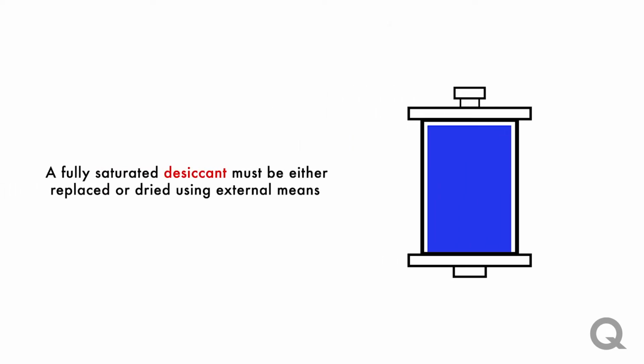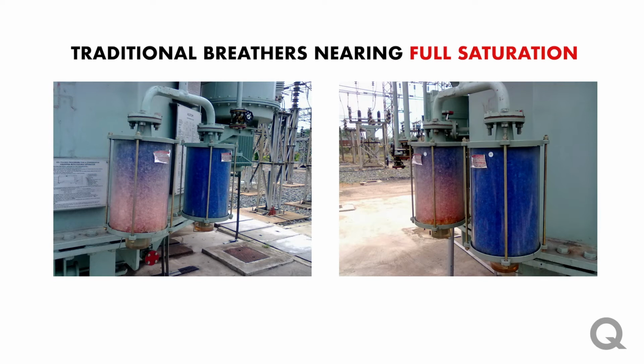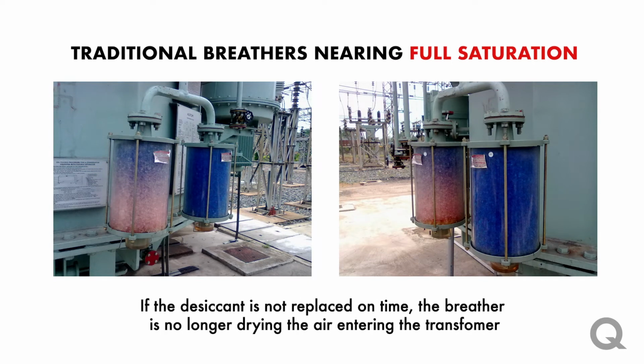So traditional breathers are essentially just a container with silica gel desiccant that the air passes through as it enters the transformer. This desiccant changes colors as it becomes saturated, and once it's fully saturated, it needs to be either replaced or dried using external means, which is costly. It is very hard to determine when the desiccant becomes fully saturated, and if this maintenance step is missed, the breather is no longer drying the air entering the transformer.